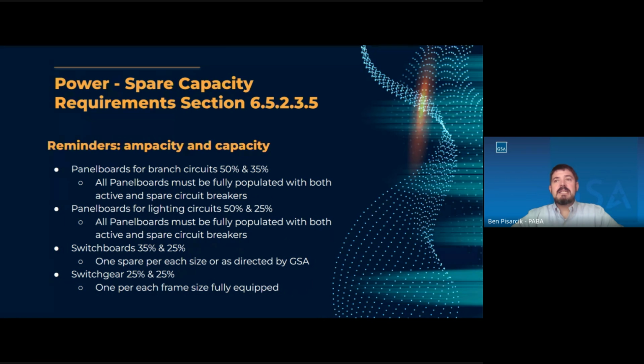So the ampacity is the load on the panel itself. You could have a panel board that was completely full of circuit breakers, but they were all lightly loaded and there would be ampacity on that panel board. Or you could have a panel board that was completely maxed out from a load perspective and still have spaces or spares in that panel board. So that's the difference between the two, and we need both. Otherwise, we can't tap into those at a future date to feed for a renovation or something like that.